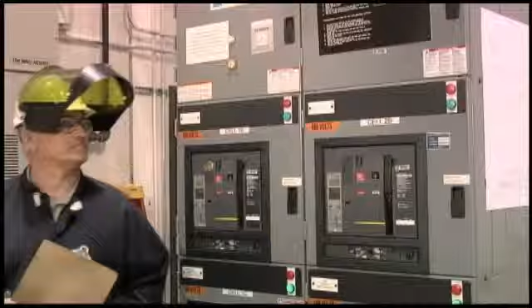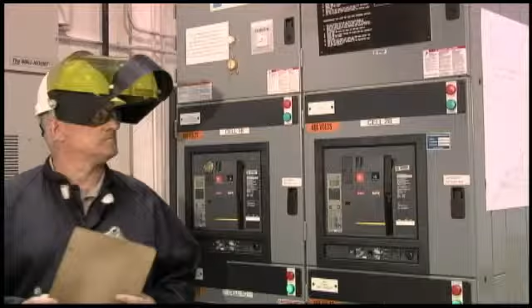The second way you will know the required distance is through the use of warning labels. These labels give you several important pieces of safety information. They communicate the voltage and the arc flash hazard boundary. According to this label, you are to stay at least 4 feet away from the equipment while any task is being performed that might initiate an arc. In general, that means a 4-foot boundary must be maintained any time work is being done involving that piece of equipment. Or you can use tools and devices to reduce a designated piece of equipment down to level 2.